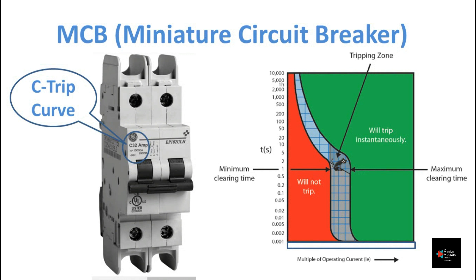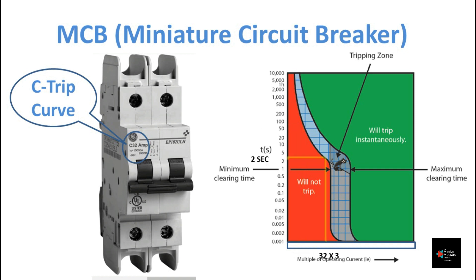The tripping curves of MCBs are denoted by alphabets such as B, C, D, K, and Z, along with their rated current. It's easy to understand from the curve at which current the MCB will trip. For example, for a 32A MCB, if 1.5 times the rated current flows, the MCB may trip in about 50 seconds. But if 3 times the rated current flows, it may trip in 2 seconds.